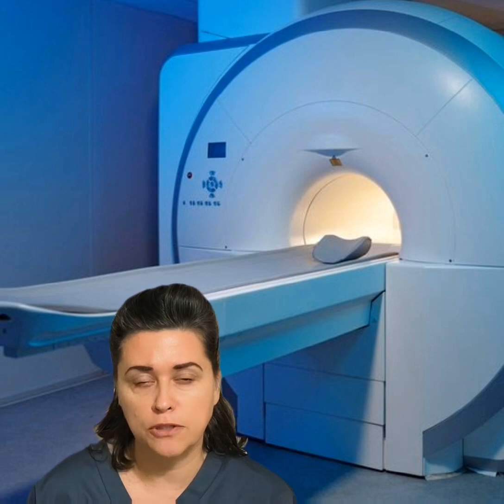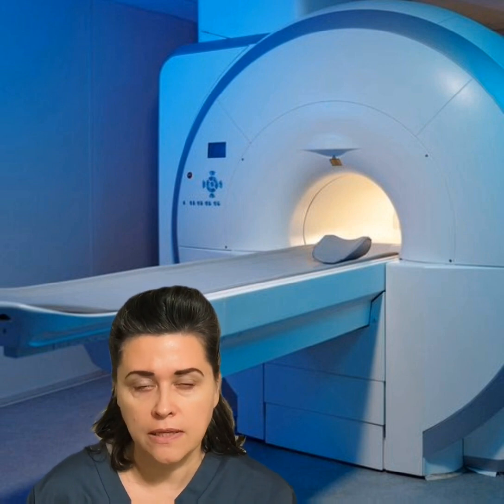Equipment inspection is a broad inspection. It includes inspection of coils, cables, monitoring devices, even door seals. And as for geometric accuracy, it's a very important test because the scanner has to accurately tell the object's height and width within the slice in order to produce a quality image.